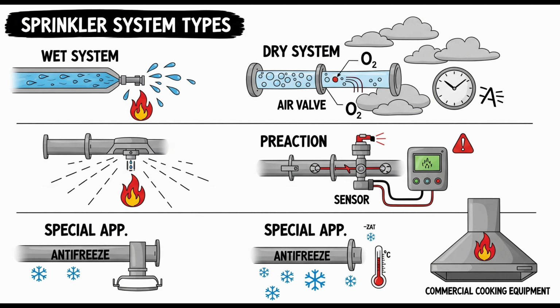Let's focus more closely on pre-action systems now and their different types. You mentioned three. Right. Pre-action systems are defined by how they get water into the pipes, specifically the logic connecting detection and sprinkler operation. There are three main types specified. Okay. First is single interlock. In this type, water enters the piping network upon operation of the detection devices only. So detector goes off, valve opens, pipes fill. Simple. Simple logic, yes. One trigger of the detection system fills the pipes. Water won't discharge until a sprinkler head also opens due to heat.